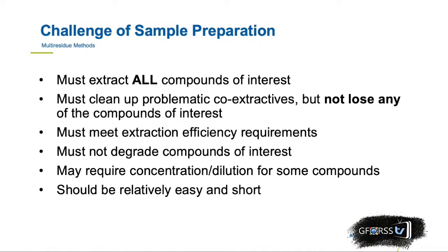Using a tandem quadrupole instrument reduces the level of cleanup needed in a wide variety of samples, but there is still a need to remove any matrix components that could negatively impact the ionization in the source, especially if it increases the limit of quantitation and the limit of detection to above the levels needed for the purpose of the method.